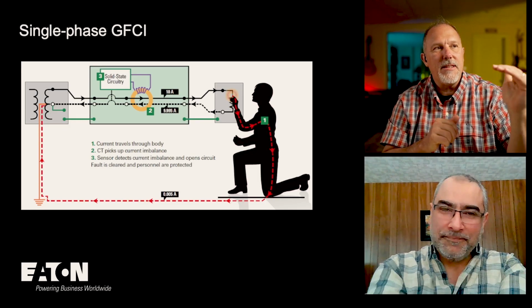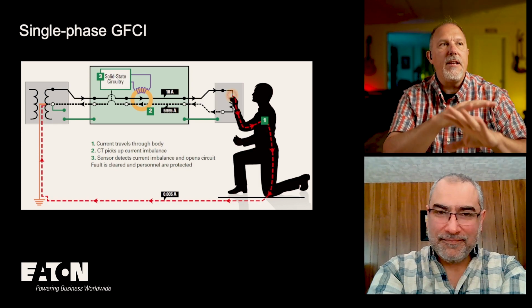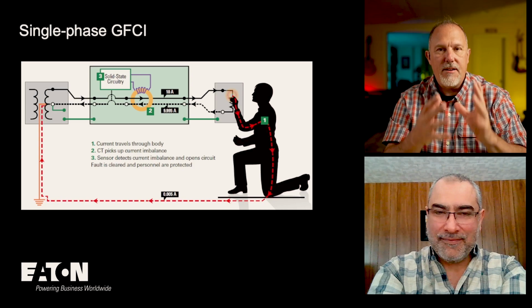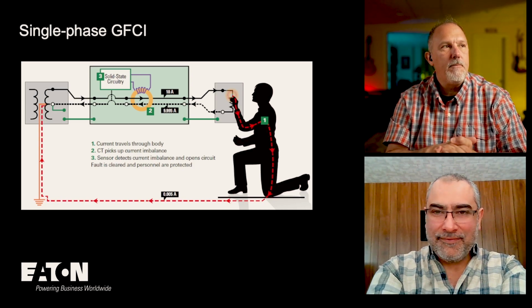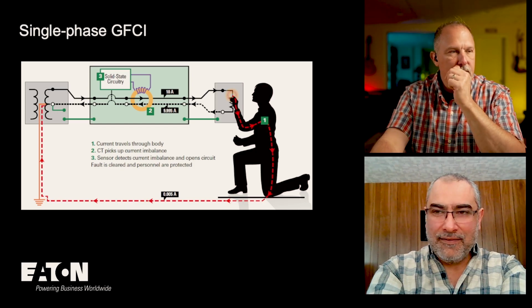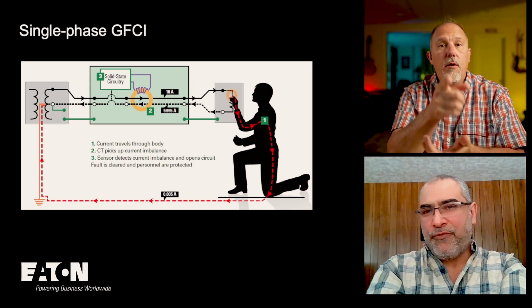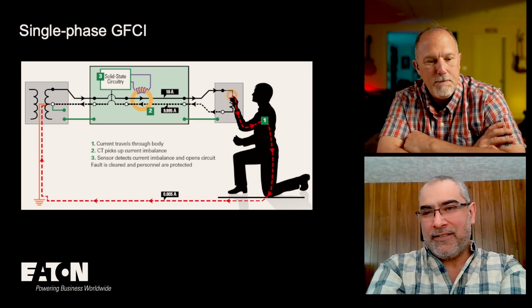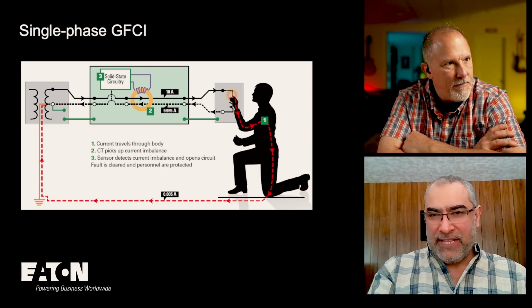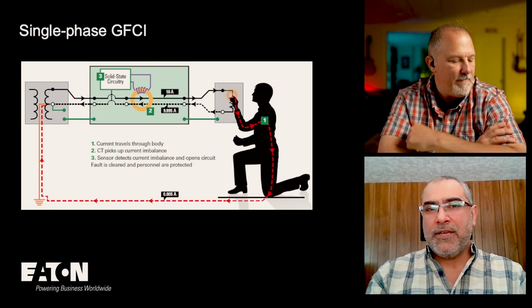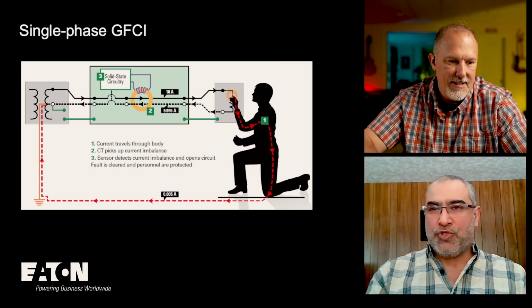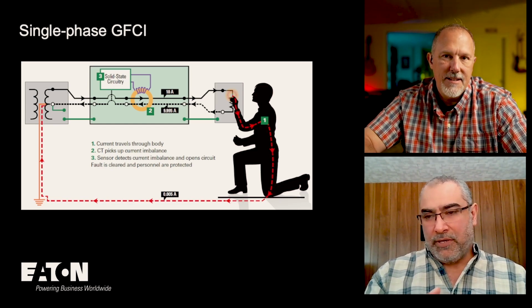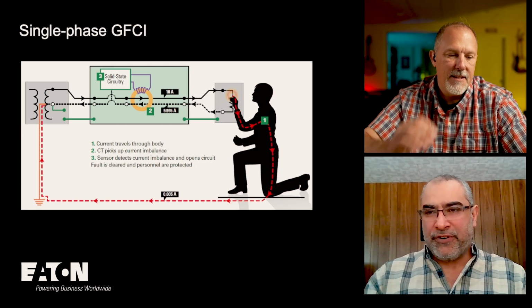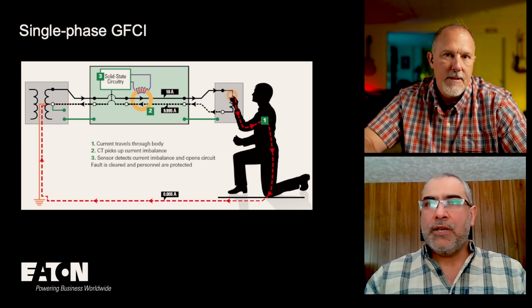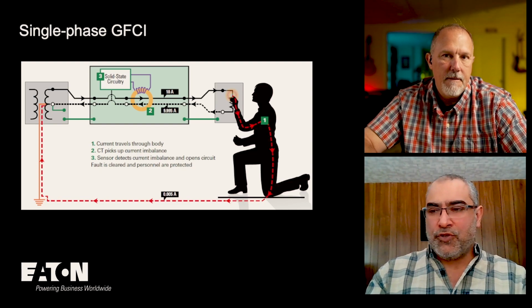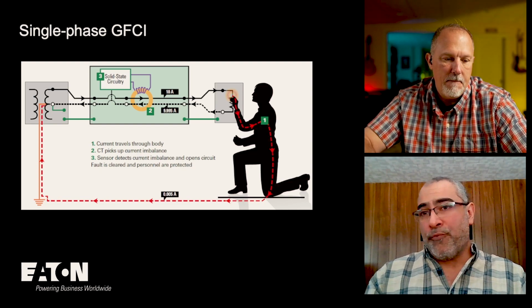So let's talk about this. We know we have the impedance of the body, and we're limiting the amount of current flowing through the body. My comment was, when you used the 400 ohms, it's interesting because the value UL uses for testing GFCIs is 500 ohms. As you may recall from the previous slides, Tom was showing that the resistance - since we're talking 60 hertz we're neglecting capacitance because it's almost open circuit, the capacitive reactance is really high compared to the resistance - so the resistance of the person is in the kilo-ohm range.